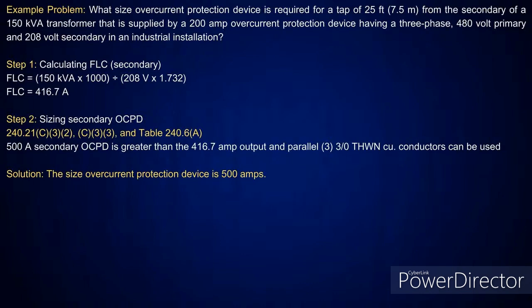This here is the gotcha, where you're just coming from the secondary side. The secondary is a 150 kVA transformer supplied with a 200 amp overcurrent device, having a three-phase 480 volt primary and a 208 volt secondary. So I'm going to do the secondary here because I already know what the primary is.